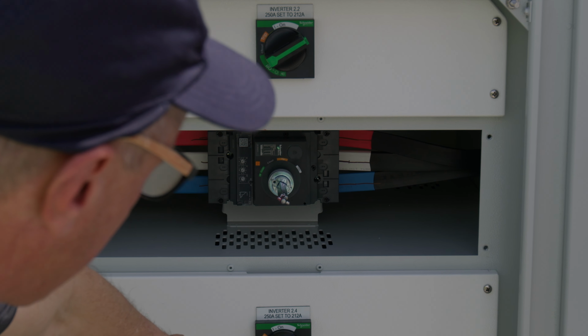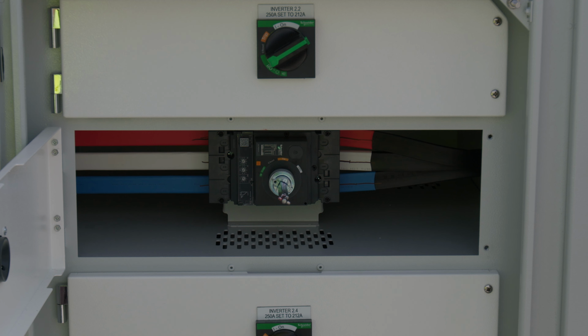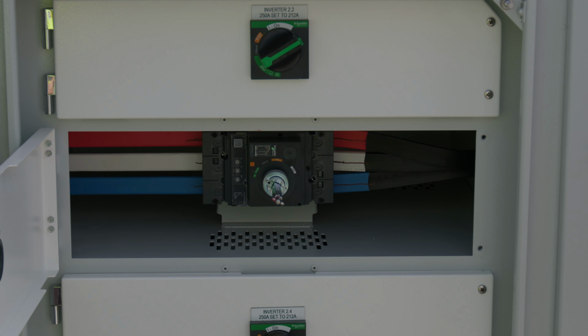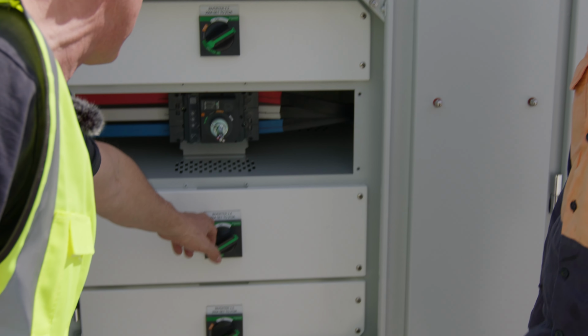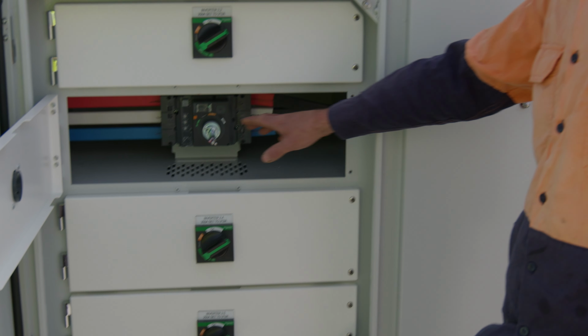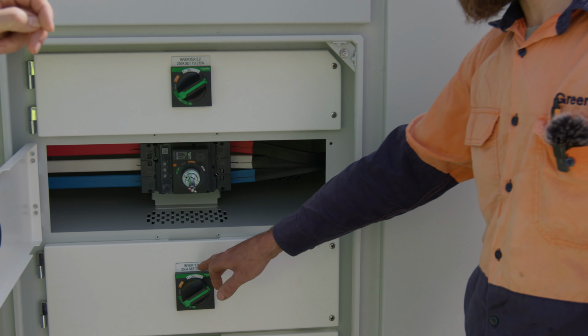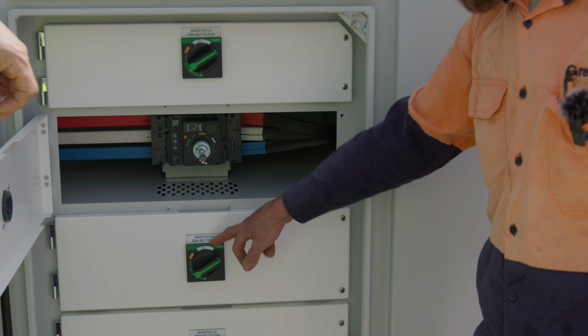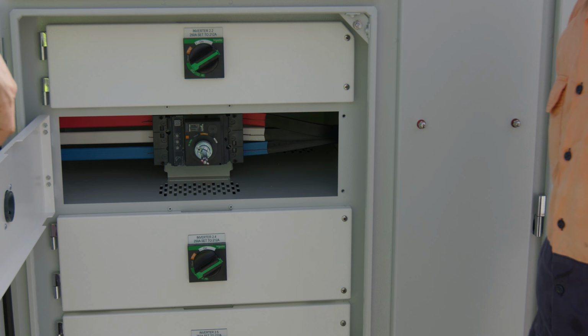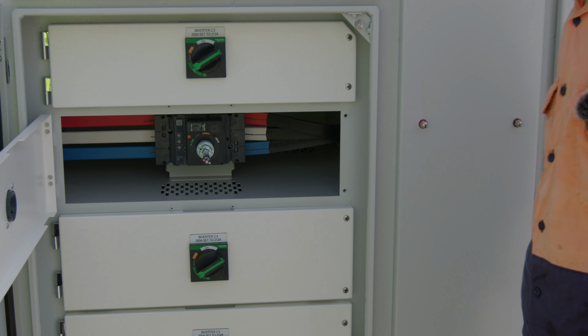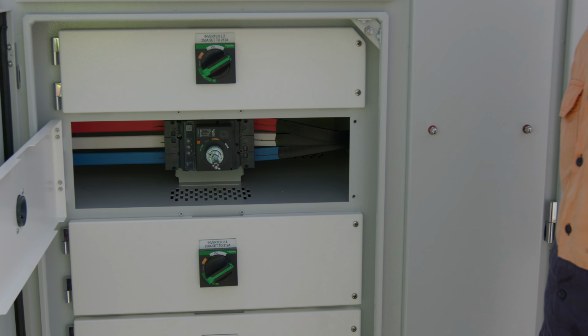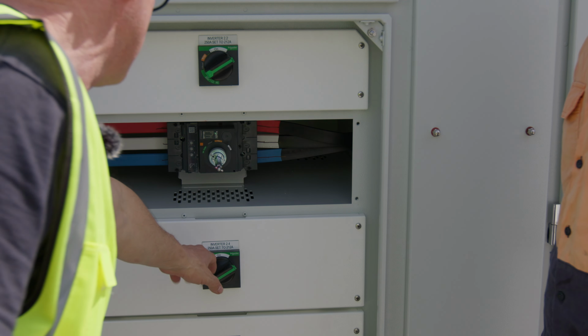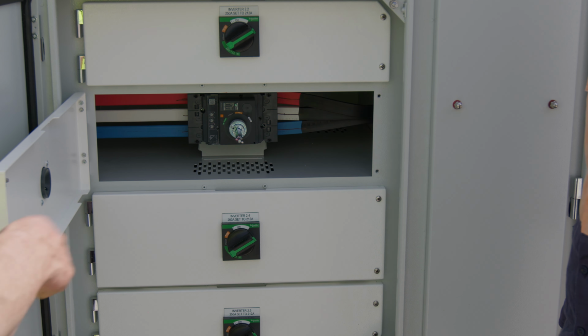So we've got a 250 amp breaker, and we've set them to 212 amps, and the reason sometimes that we do that is so that it allows us to use a particular cable that has a lower current carrying capacity than something that required the full 250 amps. Most of the time these breakers come in sizes. 250 amps is the step above. They don't really come in a 212. Correct. So to get that capacity, we just change the settings down the bottom here. We dial them down. That allows us to use, for instance, a cable that has a current carrying capacity of 220 amps. And if we left the setting at 250 amp, we'd have to use a cable that's 250 or greater in regards to current carrying capacity.